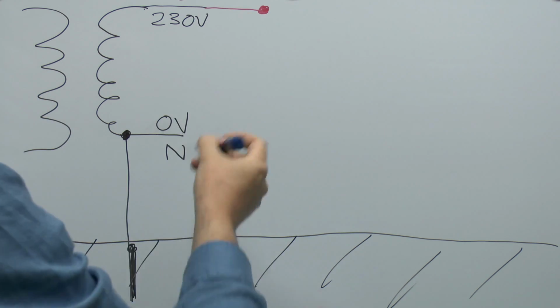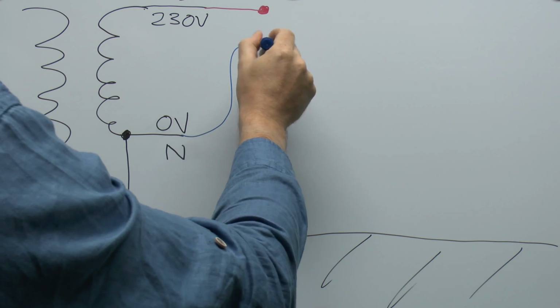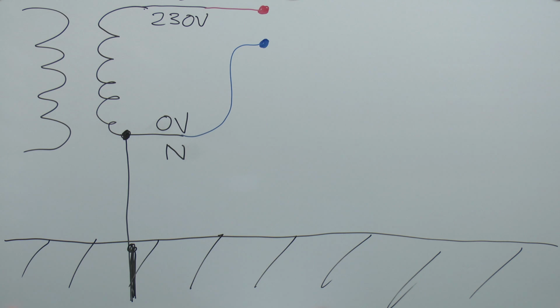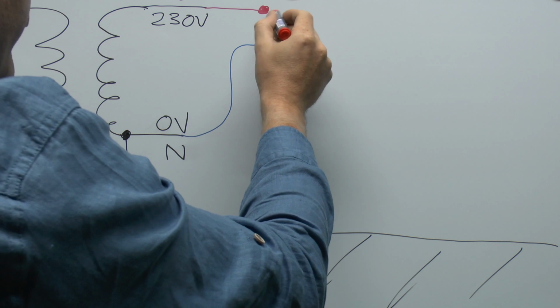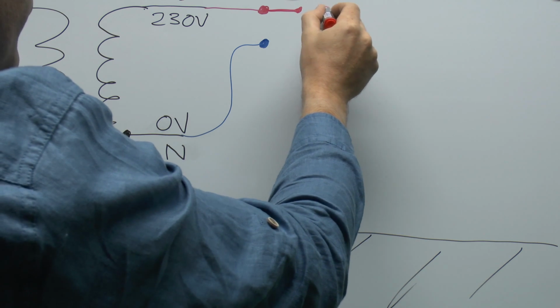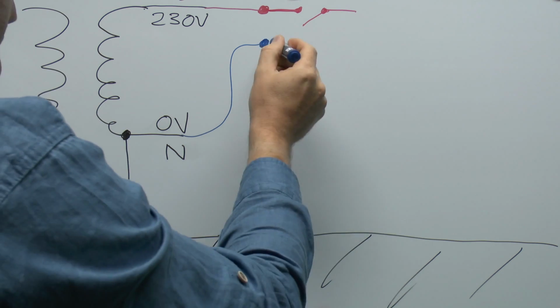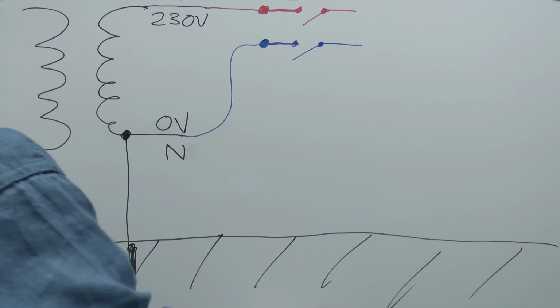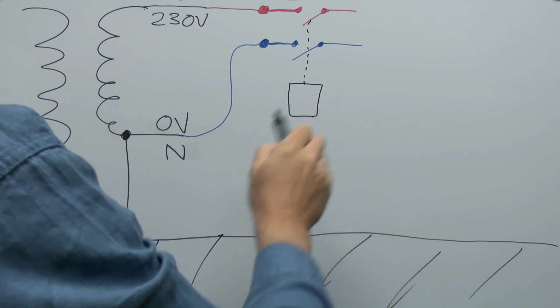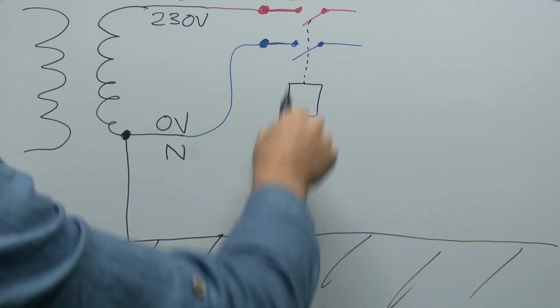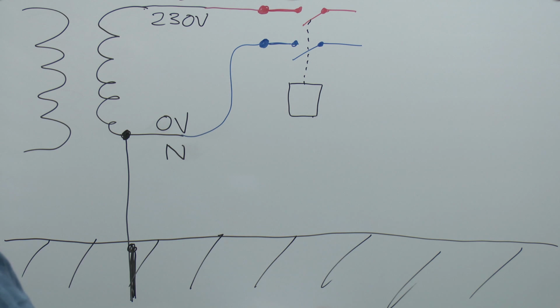we can have, say, the line coming in here, and then we'll say have the neutral coming in alongside. And all that's in an RCD is, first of all, a switch of some kind. So we'll just draw a switch in there. Generally, these are double pole switches, although there's no particular reason why it wouldn't be a single pole also, but we'll draw in a double pole with some kind of actuating mechanism. Could be a solenoid or some other kind of actuating device just to trip the switch when necessary.